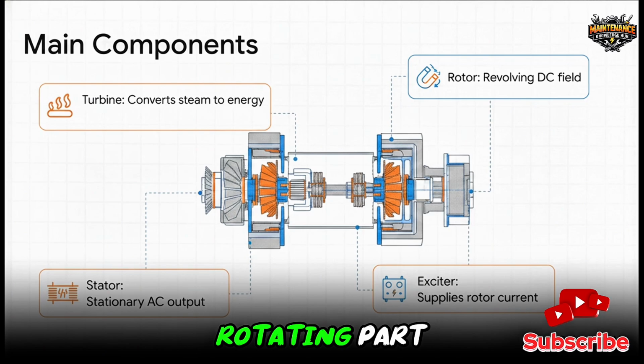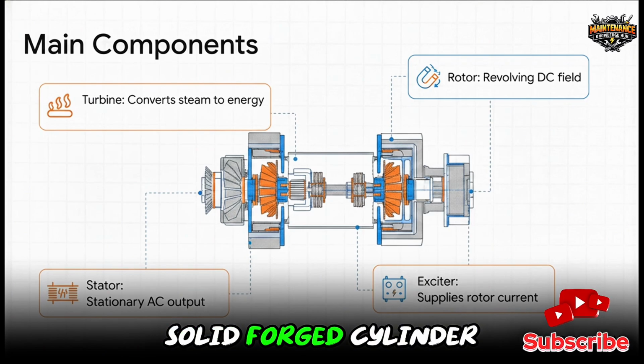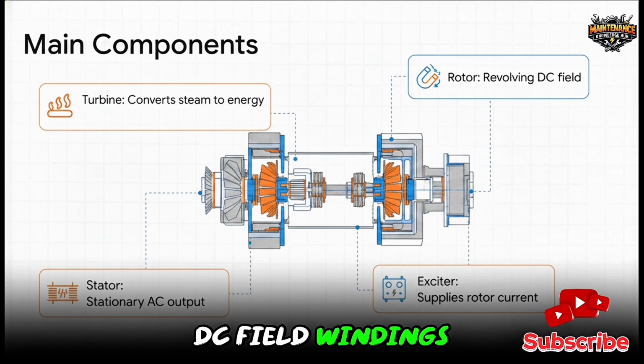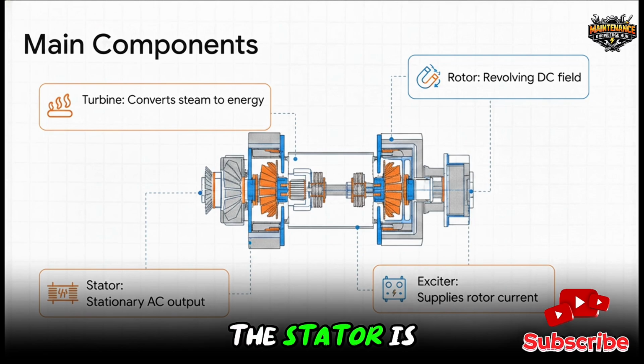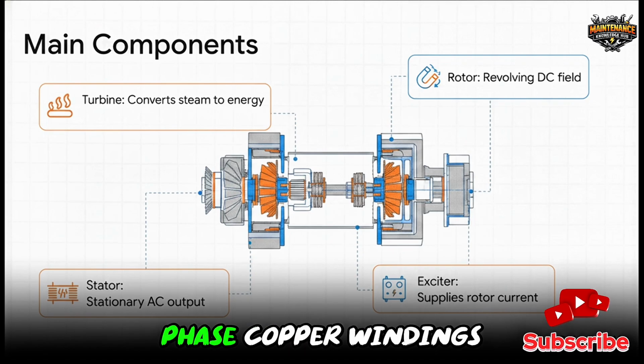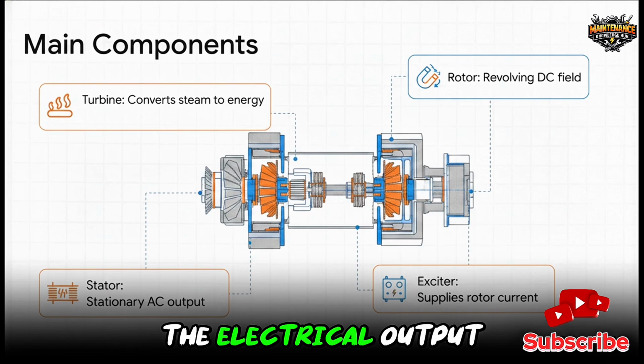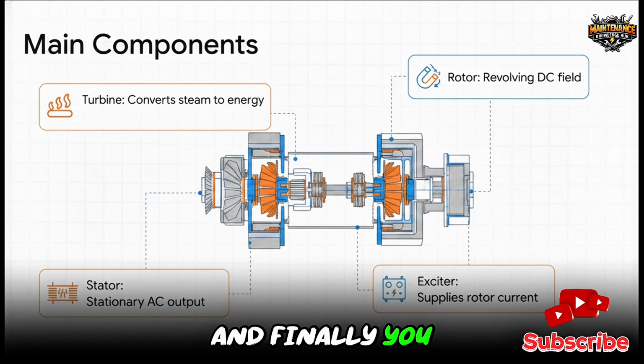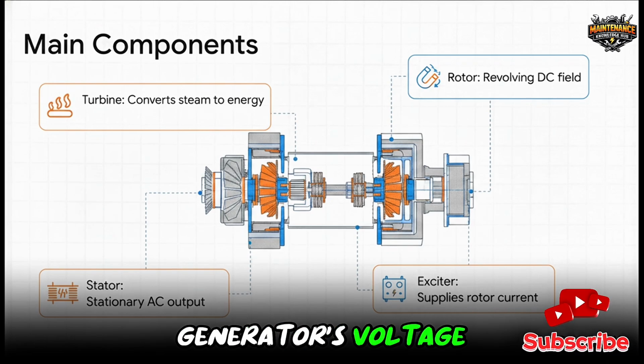The rotor is the rotating part, usually a massive solid forged cylinder containing DC field windings to produce the magnetic field. The stator is the stationary outer frame holding the 3-phase copper windings that actually generate the electrical output. And finally, you have the excitation system. Think of this as the control center, which can be brushless or static, supplying the essential DC current to the rotor to maintain the generator's voltage.